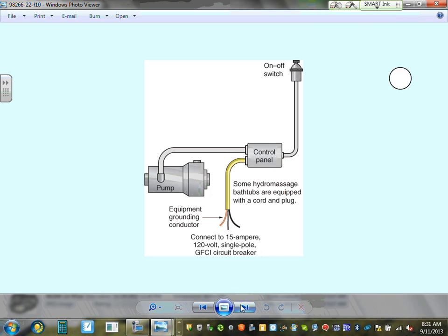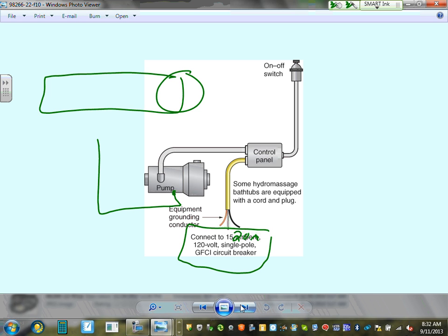Now the last thing, guys, is the hydro massage bathtub. Typical application. It says here 15 amp. Connect to a 15 amp 120 volt single pole GFCI circuit breaker. Typically, what we do is we use 20 amp for them. We provide a 20 amp dedicated circuit for them, and we grab the frame and tie it to the water pipe, bond it with number 8 AWG copper. And can you guys see the words GFCI receptacle?